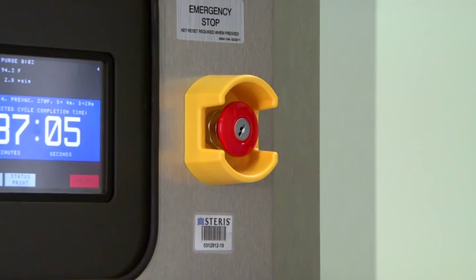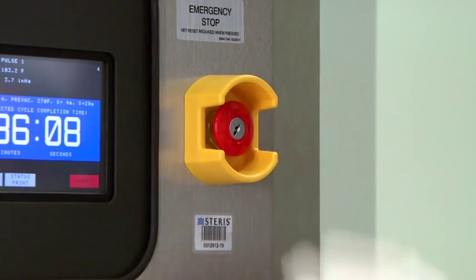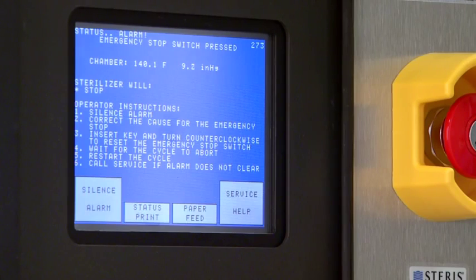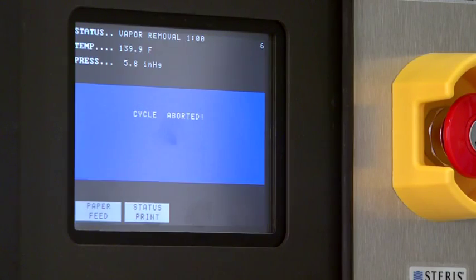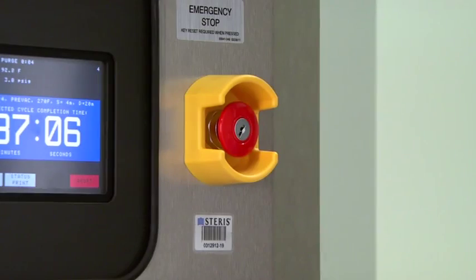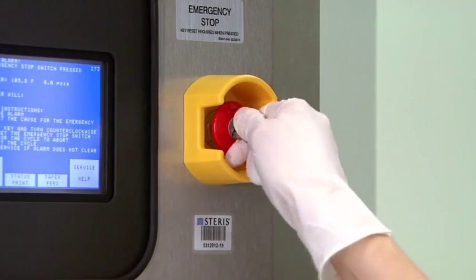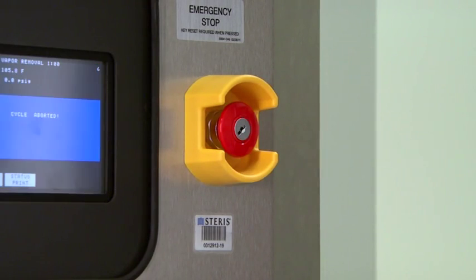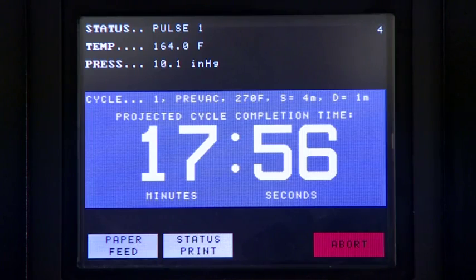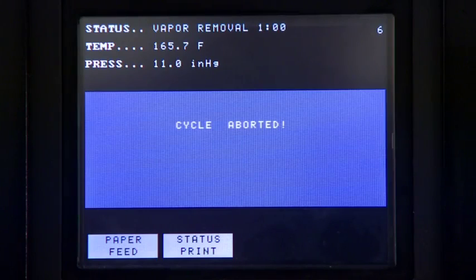Another important safety feature to note is the emergency stop switch. This feature shuts the sterilizer down completely in an emergency situation. Pressing the emergency stop switch disconnects power to the door and valves, causing the door to stop and critical valves to close. An alarm is generated when the emergency stop switch is pressed. An emergency stop key is required to reset the switch. Refer to the alarm procedure in the operator manual to clear the alarm. Do not use the emergency stop switch as a start-stop switch. To properly abort a cycle, press the Abort button on the sterilizer display.